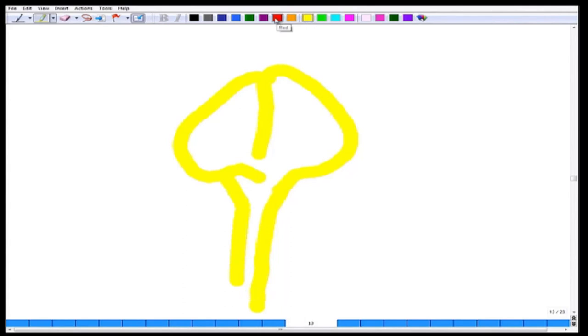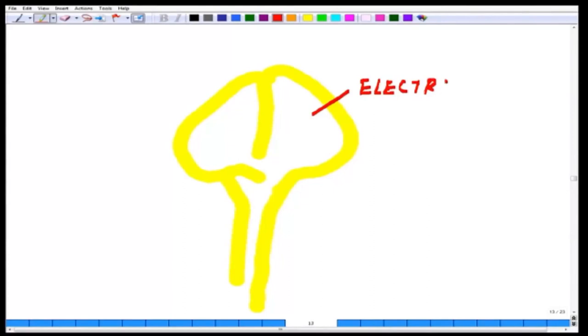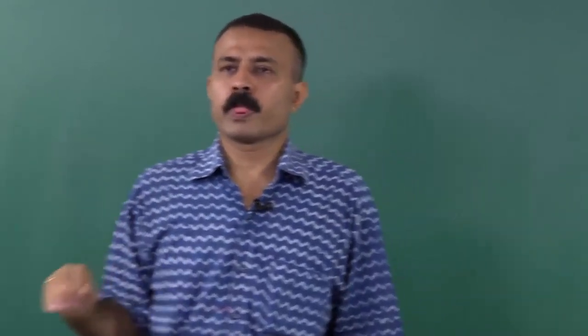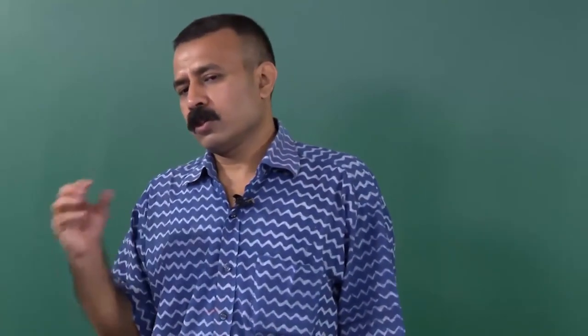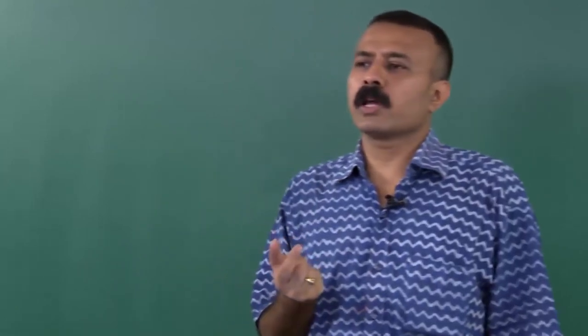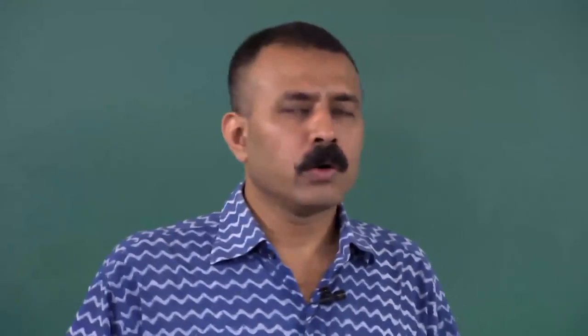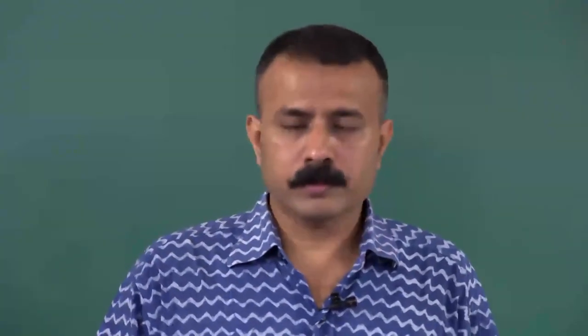When you want to implant an electrode in brain tissue, the problem arises because the electrode out there faces real-life challenges. You have to consider all the challenges this electrode is going to face. First of all, this electrode is in a dynamic ionic system. In a dynamic ionic system, the electrode material must be so inert that it does not get corroded or damaged because of the ionic milieu — there are sodium, potassium, chloride all over the place.